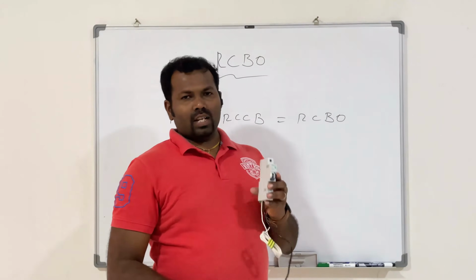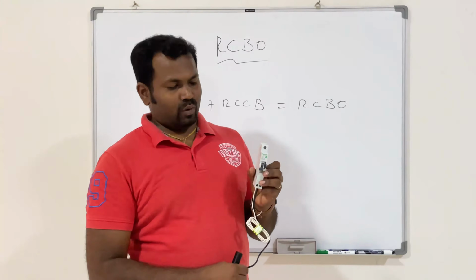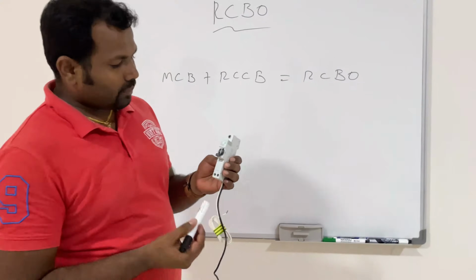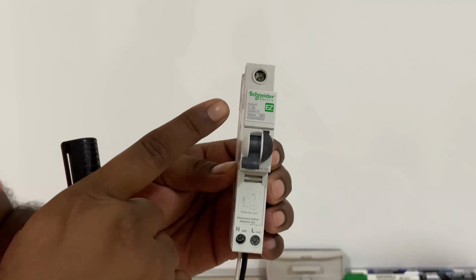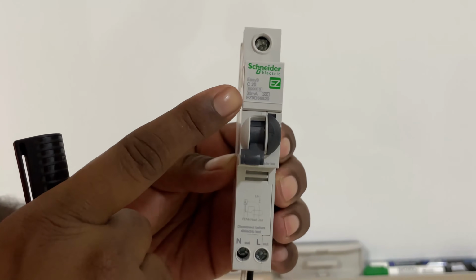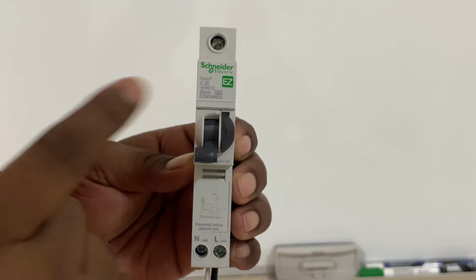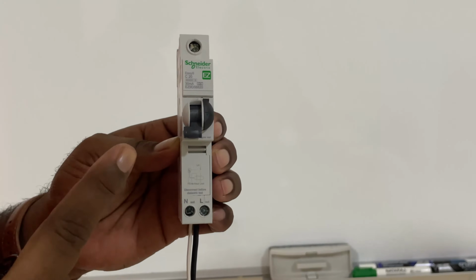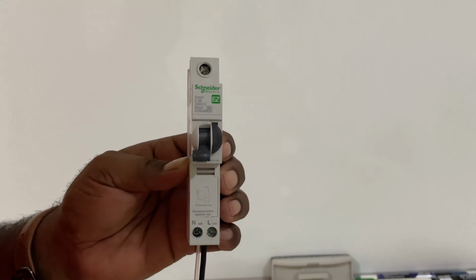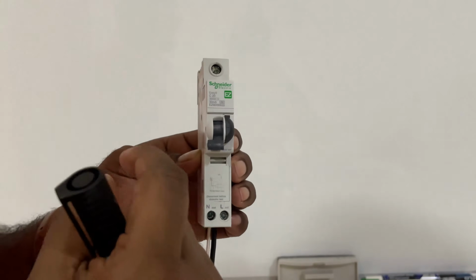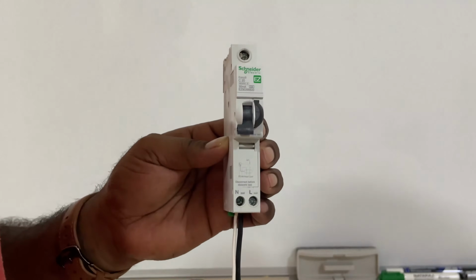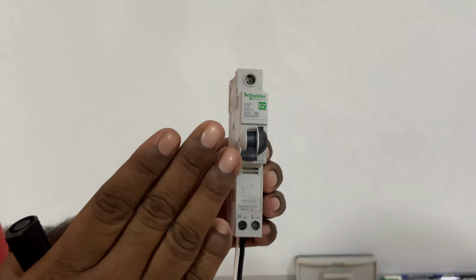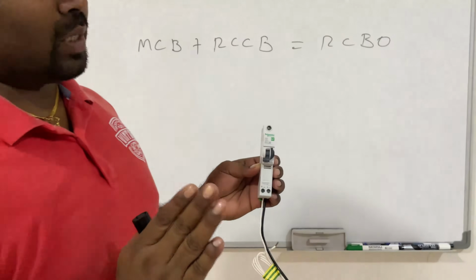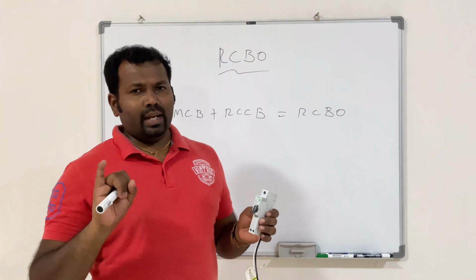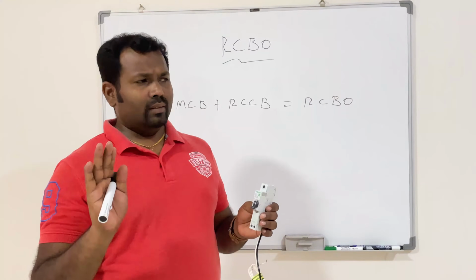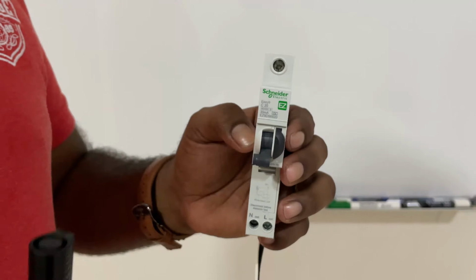Now we will see an RCBO, how it is designed and how it will work. This is one RCBO, Schneider make. You can see the specification mentioned: C20, 30 milliampere and 6000, that is 6 kA. C is the tripping curve for short circuit protection, and 20 is the ampere rating for overload protection. 6 kA is the breaking capacity rating, and 30 milliampere is the earth leakage protection range. So the RCBO specification is mentioned with overload current rating, short circuit curve type, kA rating and leakage current capacity.